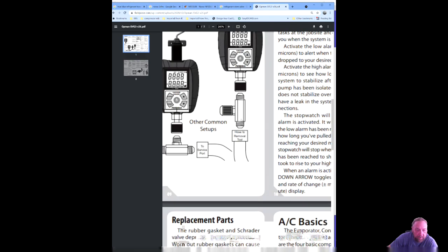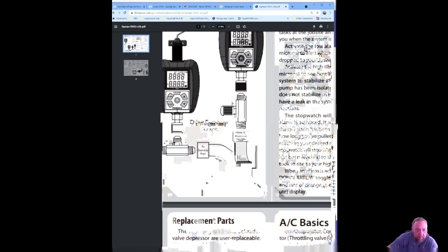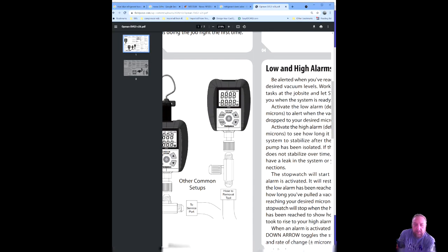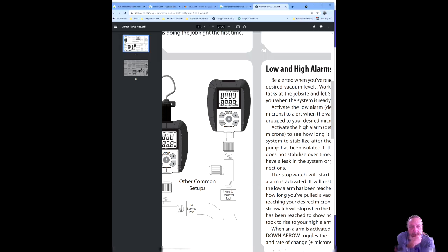And then what I do is I turn the vacuum pump back on and I pull vacuum out of all these hoses, including the gauges. So when I open up my Freon tank, I have no air in my lines. I have this T fitting here, and I use that vacuum and the T fitting to pull my vacuums and everything. But when I shut it off here and I go to charge, Freon doesn't go back out my pump area. Does that make sense?